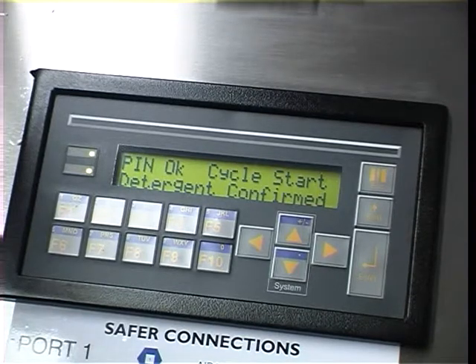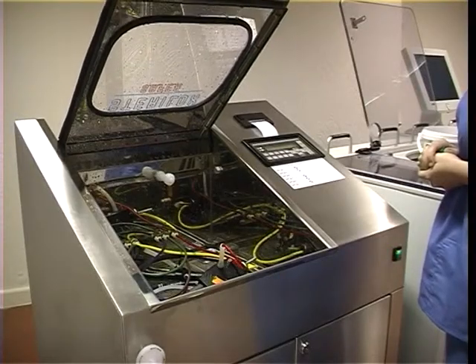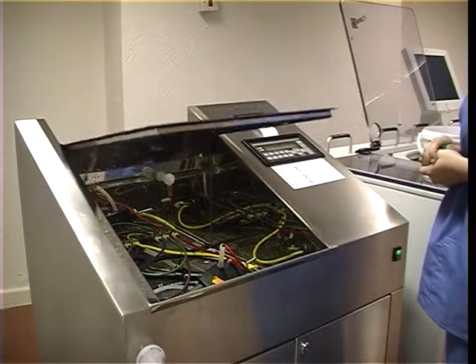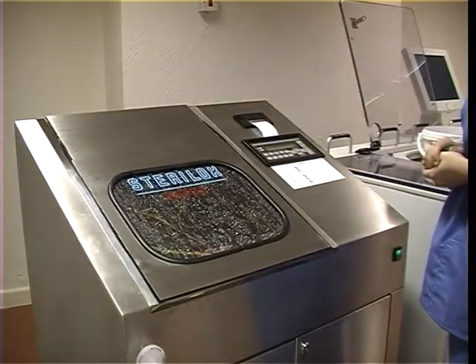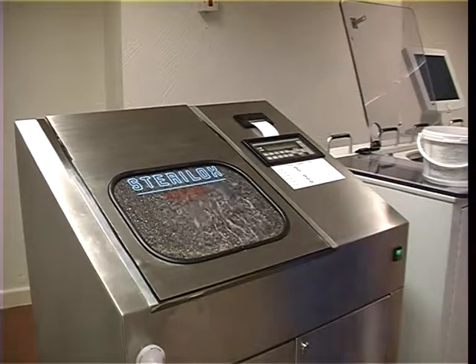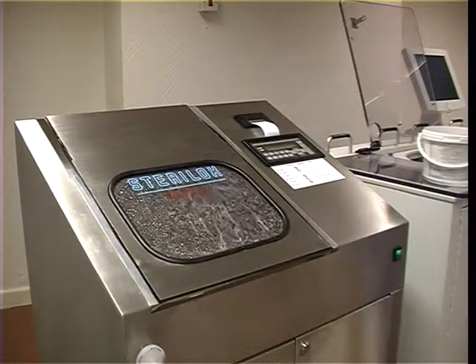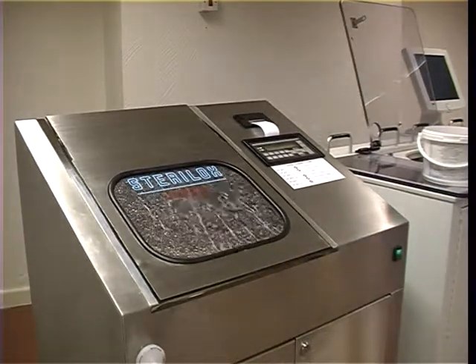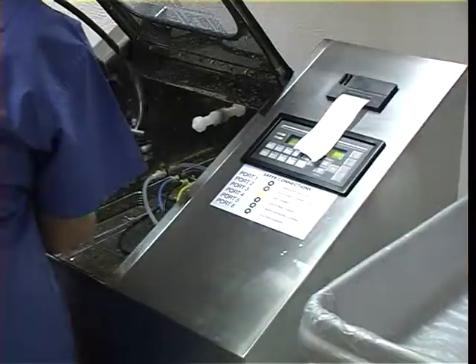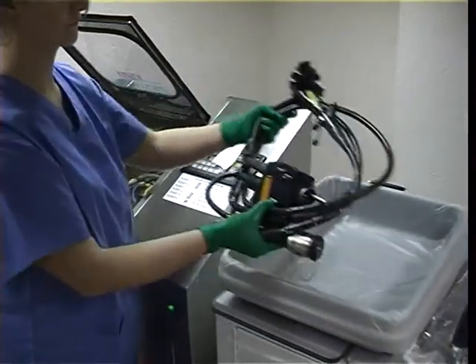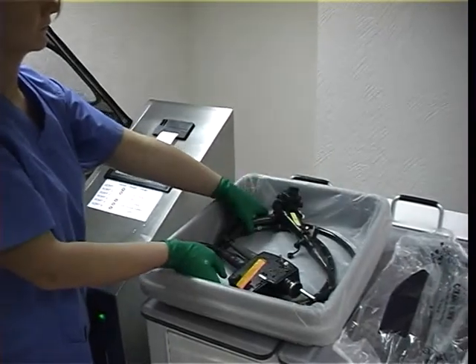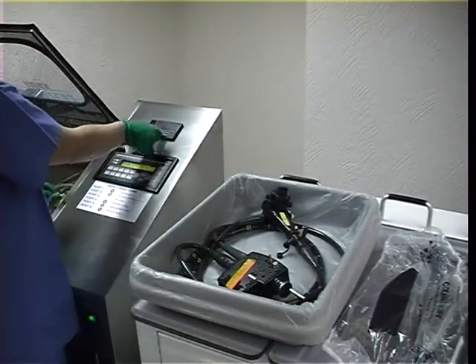Be aware, door closing. It is very important that the washer disinfector is cleaned and dried at the end of each day, and at any time that the top surface becomes wet through normal use. If regular good cleaning and housekeeping is not carried out, the machine will start to visually look unsightly and could be a possible source of cross-contamination within your department.